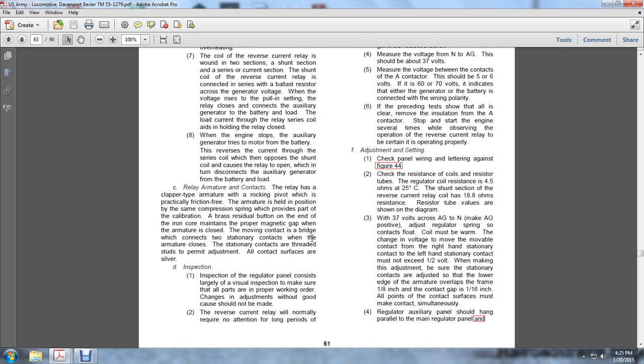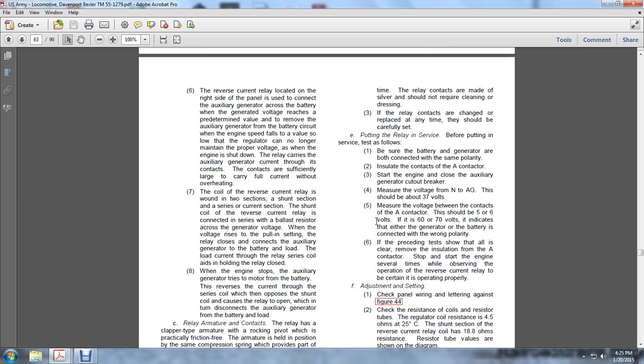Inspection: in inspecting the regulator panel, make a visual inspection to make sure that all parts are in proper working order. Changes in adjustment should not be made without good cause. The reverse current relay normally needs no attention for long periods of time. The relay contacts are made of silver and should not require cleaning or dressing. If the relay contacts are changed or replaced at any time, they should be carefully set.